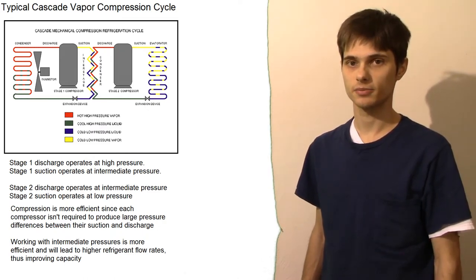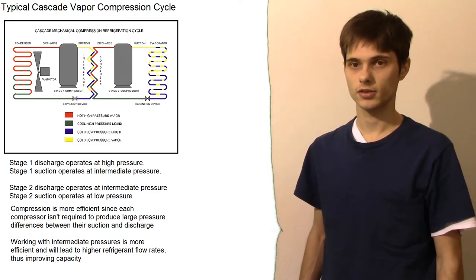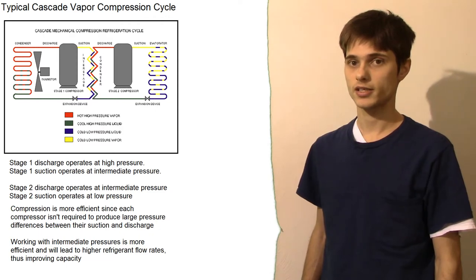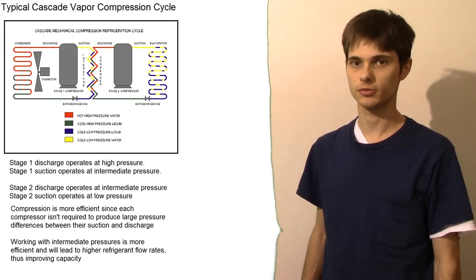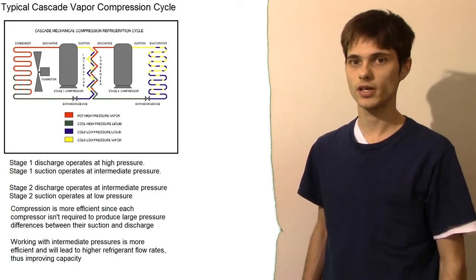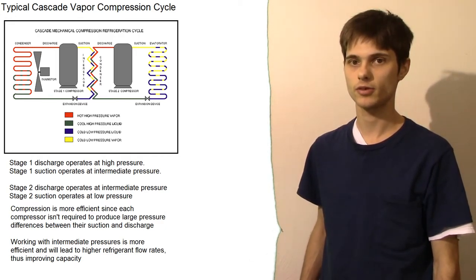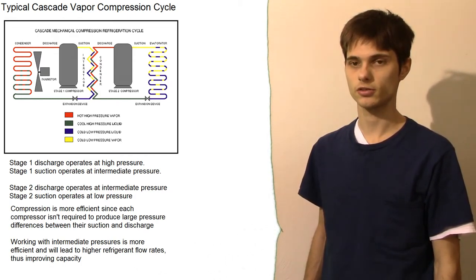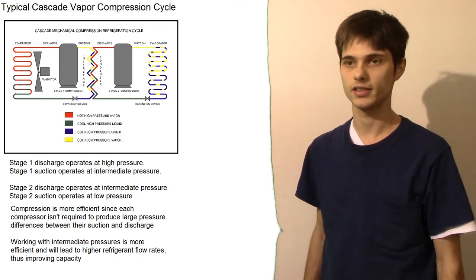In the cascade system, we talk about two cycles. One's usually referred to as a high temperature cycle and one's usually referred to as a low temperature cycle. The high temperature cycle then will take an intermediate pressure and compress it up to a high pressure. Now, the high pressure side of the high temperature cycle will be the condenser which ultimately releases the heat into the atmosphere.